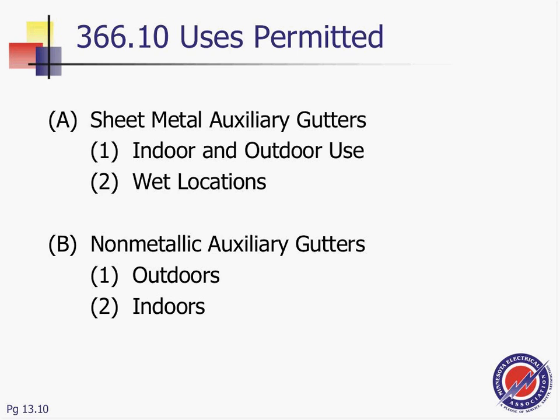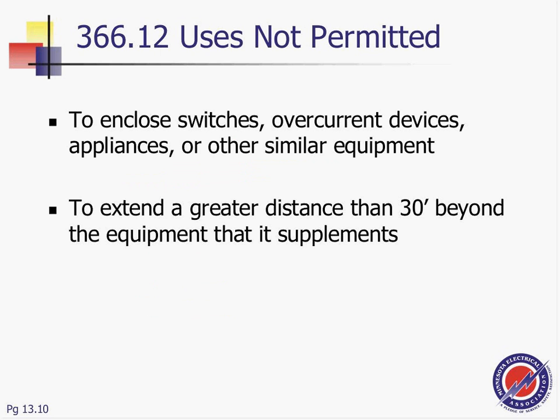Two different gutters. Sheet metal gutters, can I use them indoors? Bring it on. Outdoors, no problem if it's rated for outdoor use. In a wet location, no problem, as long as it's rated for a wet location. So I can use it indoors and I can also use it outdoors. Look at the words "not permitted." They don't want you to put switches or overcurrent protection devices in them, or similar. This is not meant to be a panel. It's not meant to be a machine.